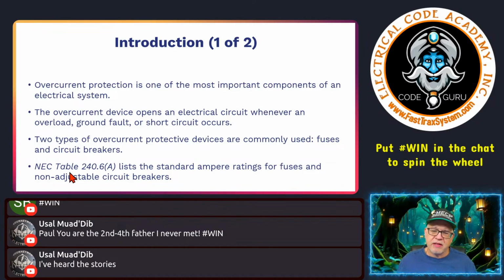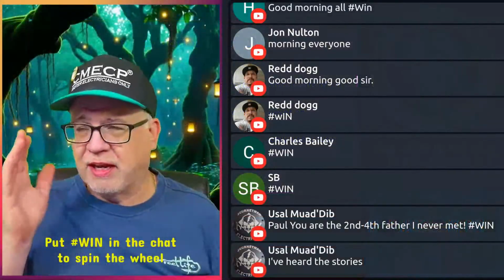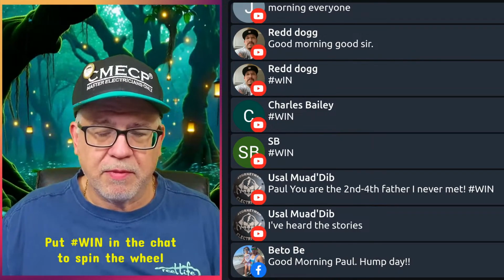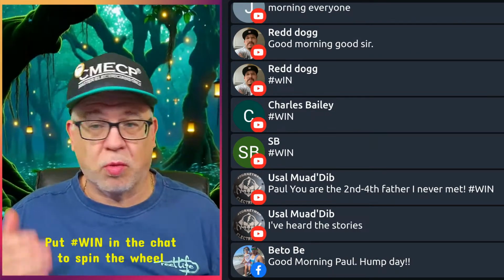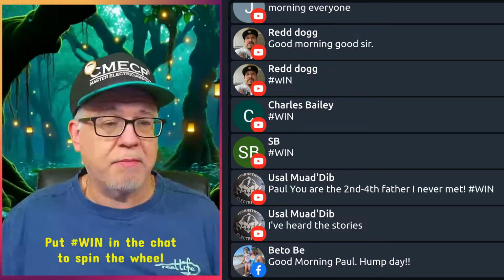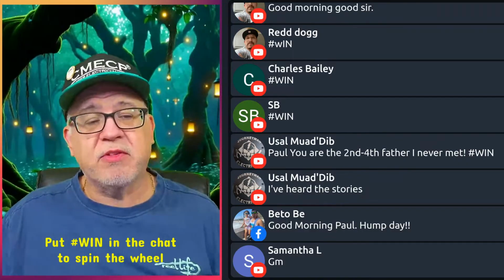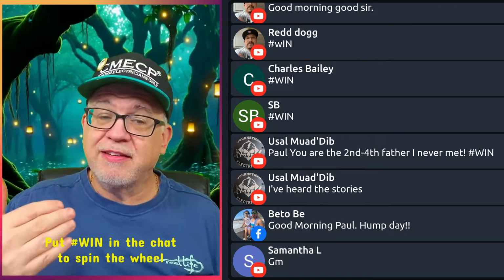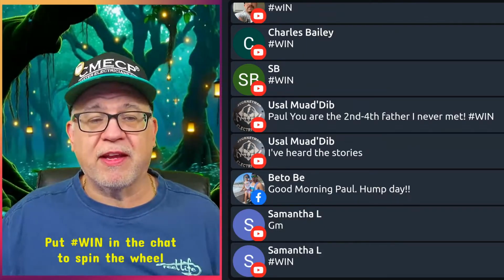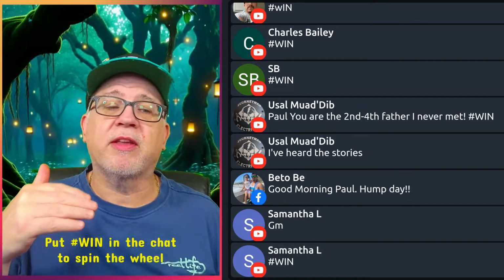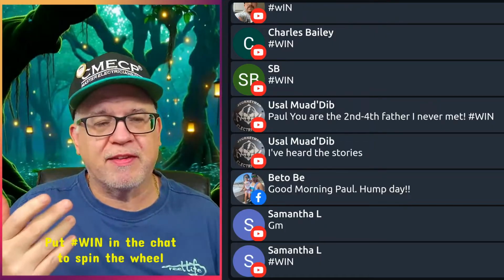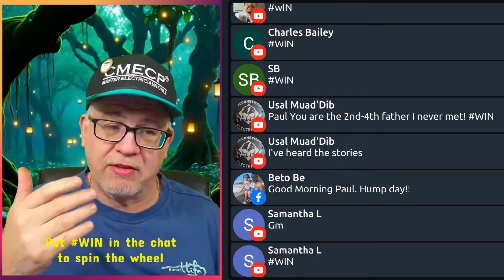Okay. So NEC Table 240.6(A) lists the standard ampere ratings for fuses and non-adjustable circuit breakers. So most of those circuit breakers that you're going to have in your panels in the houses, the stuff that you deal with, are going to be non-adjustable. It's a 20 amp, it's a 15 amp, it's a 30 amp. You can buy non-standard circuit breakers. You've got standard in 240.6(A), and don't lose sight that you can use non-standard. Now, when the code references things like 240.4(B), where we can go to the next standard size, that's when you go to 240.6(A), because you can always go to the next non-standard size that may be less.